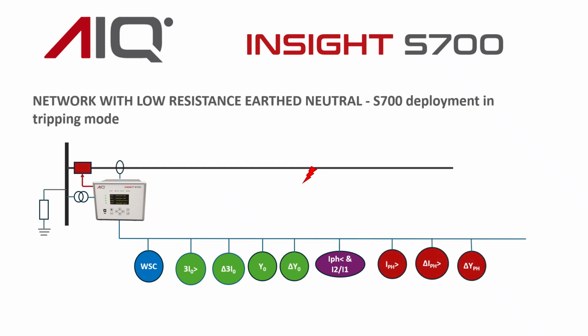If S700 is deployed for tripping in resistance earth networks, phase fault detection algorithms such as phase overcurrent can be enabled. Again, auto reclose scheme is available to restore power after tripping if the fault is found to be transient in nature.